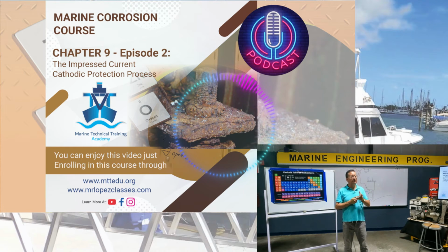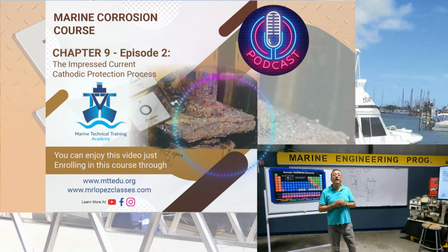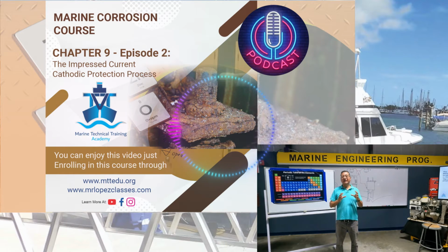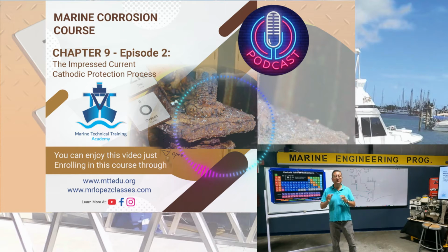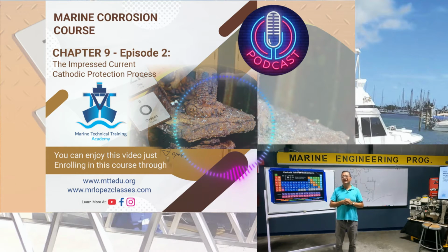This is the idea. You have here the controller, the DC controller. You can create a DC controller in different ways. With a rectifier, you rectify AC current into DC, and you use that DC current. Or with solar panels, you collect the DC power into batteries, and on the battery you connect a controller like the ACR, you remember, and you send DC current into the system. Different possibilities. But the solar system is commonly used in the oil companies to protect the pipes that transport the oil from one city to another city.